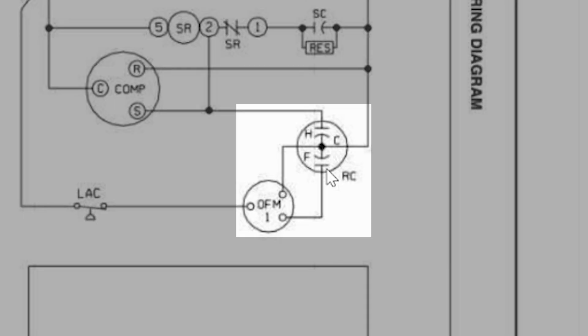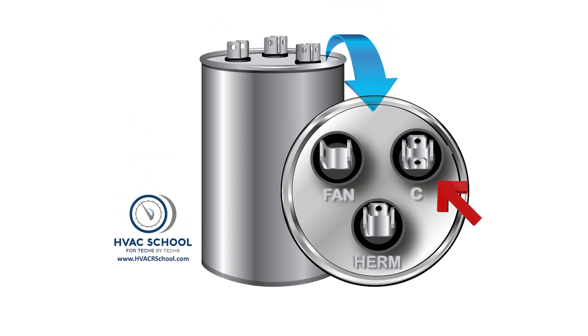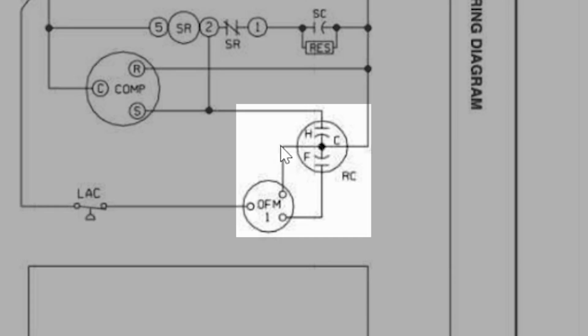Now we're also going to see, when we go over to our capacitor, our capacitor has three terminals. It has H or Herm, F or Fan, and C, which is our common terminal. And our common terminal on this capacitor is going to connect to two different things.